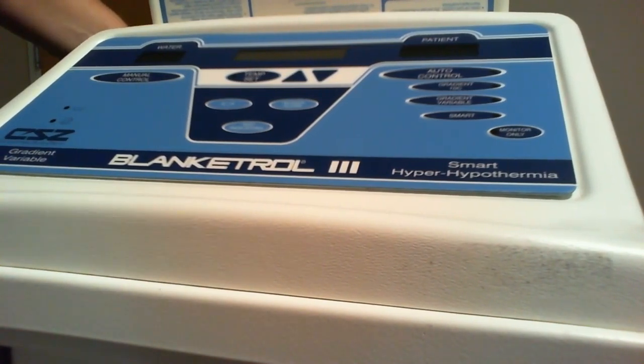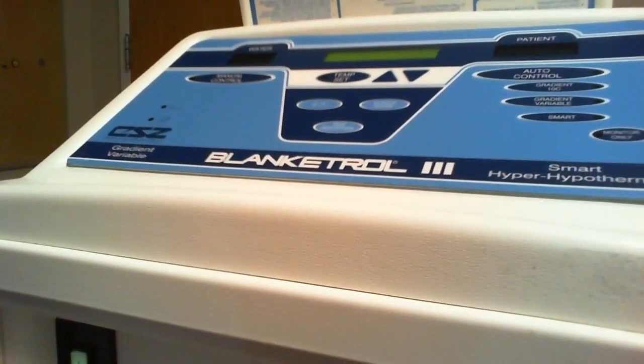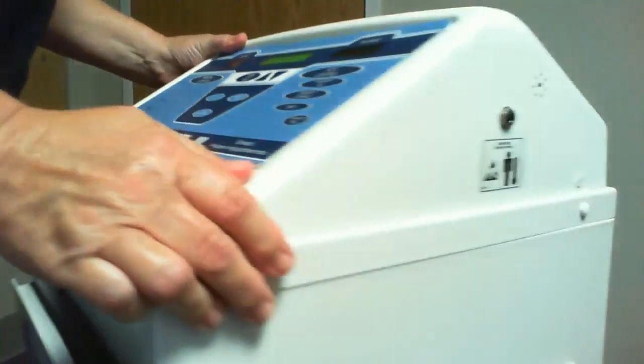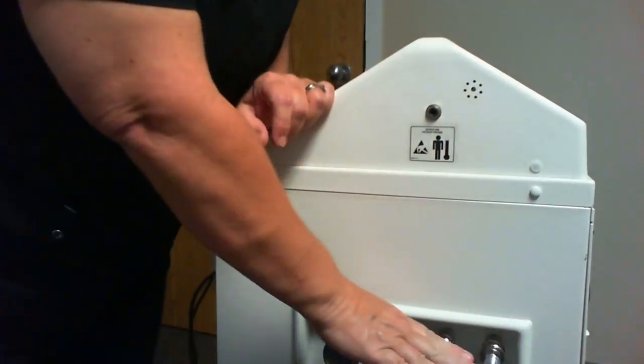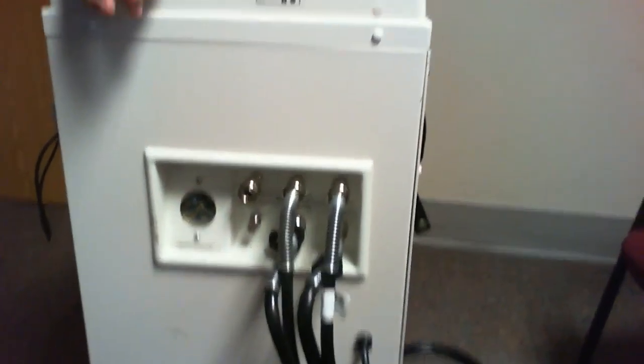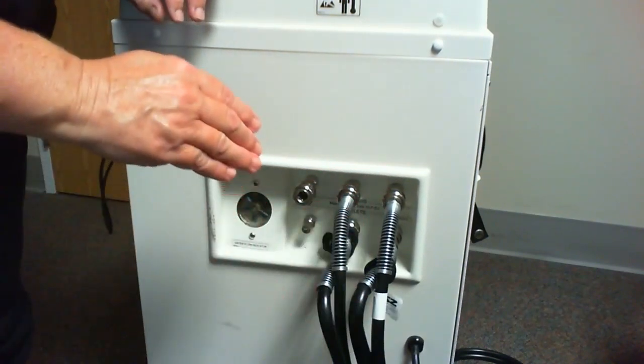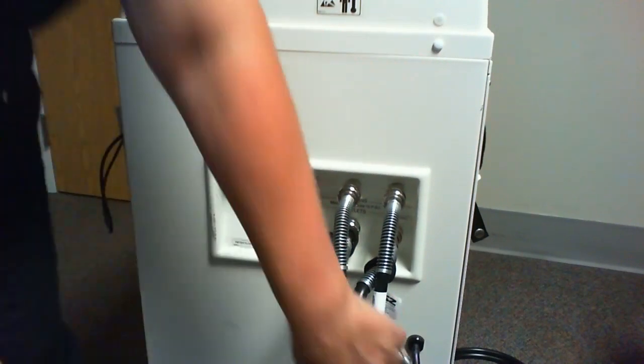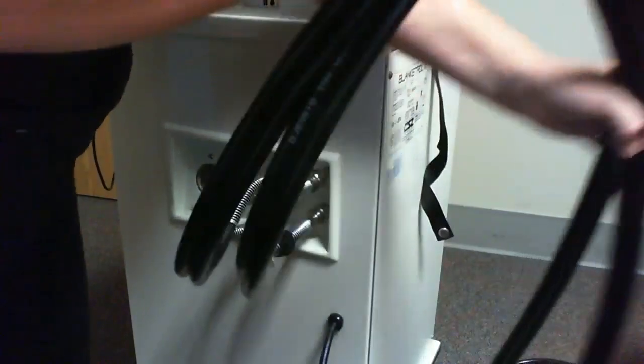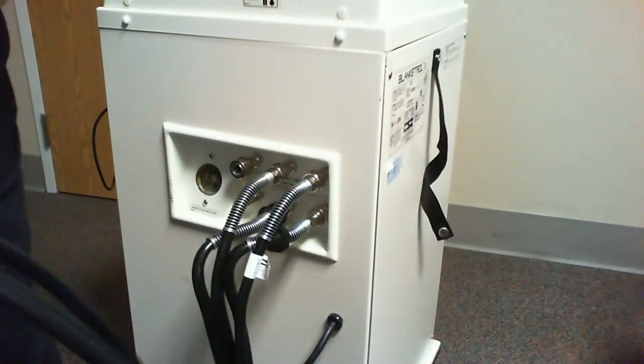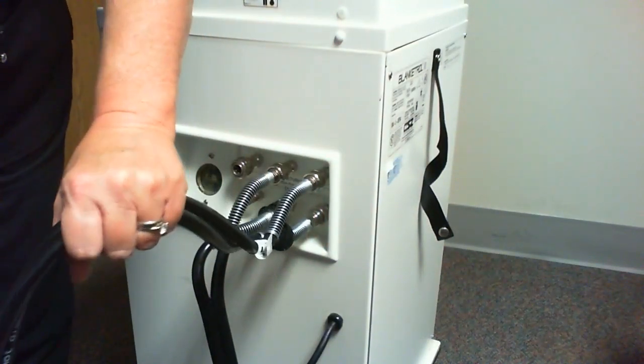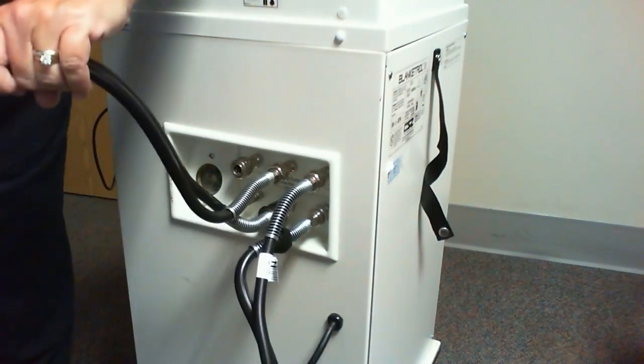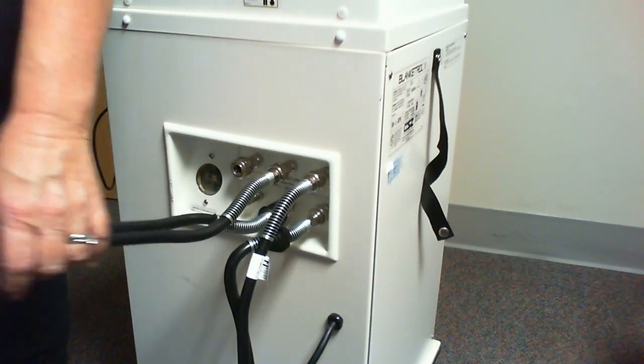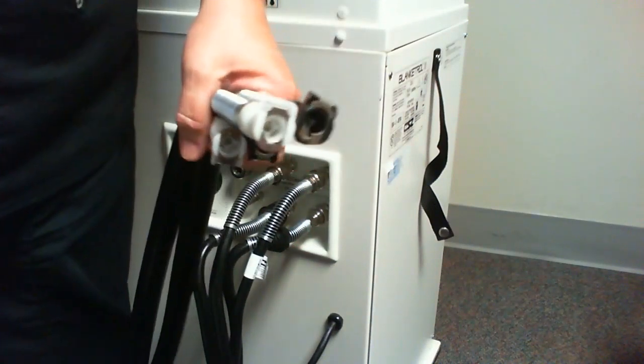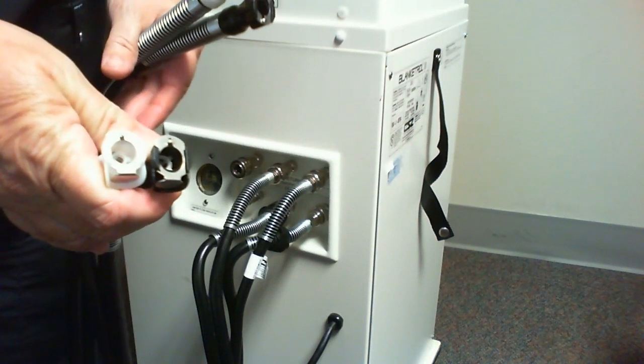I am going to now come right here and turn my machine on. I am now going to come to the side, so the opposite side, and look down here. So I'm going to have a blanket beneath my patient and above my patient. So I need to have 2 sets of cables. So this one here is going to go to one blanket below the patient, and this one is going to go to a blanket above the patient. So it doesn't matter which one goes where. And you will see that there are connections. One is an in and one is an out.